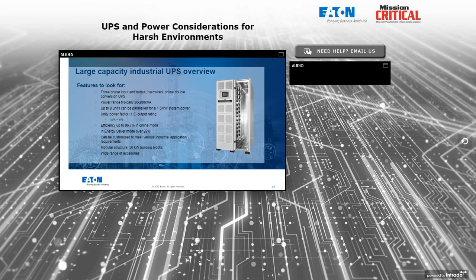Customization to meet application requirements. I need one transformer, or I need two transformers, or I need a high capacity rectifier, but I don't need a high capacity inverter. The ability to customize on the fly is very valuable because no client wants to over-feature a UPS with capabilities and features that they won't need or don't plan on needing in the future. So this particular one shown here uses 50 kilowatt building blocks and can have four 50 kilowatt UPSs in this one enclosure, which is about the size of a refrigerator, about 36 inches wide. And then also a wide range of accessories: output distribution, custom input filtering, special air filtering on the front and possibly the top, and the ability to deploy this box in a larger exterior box with climate controls and special filtering, for example, and maybe even extra batteries in that same enclosure. It's all about the ability to customize.